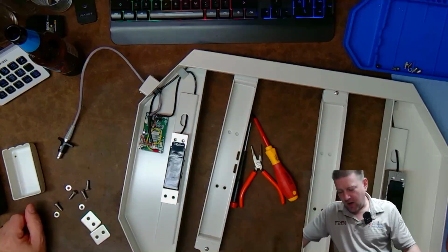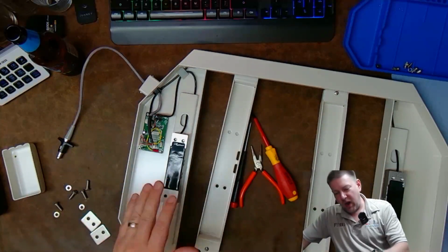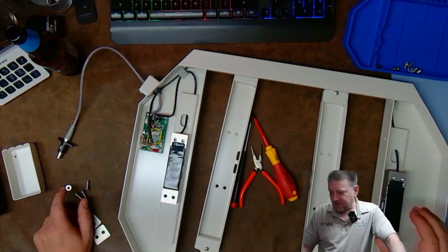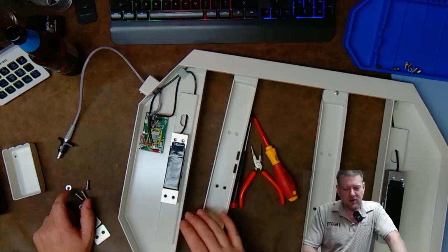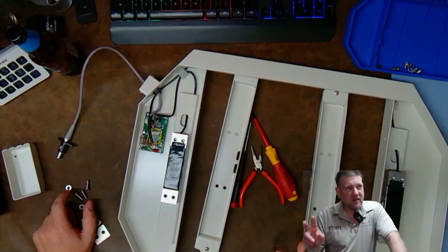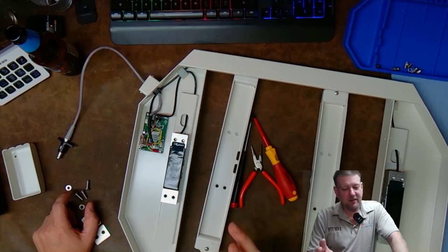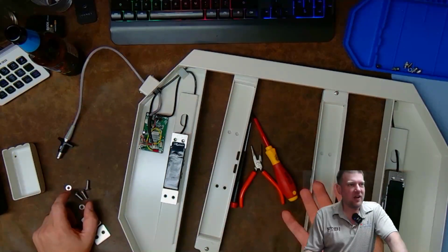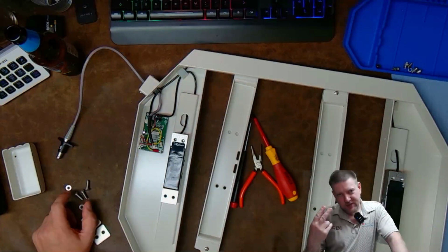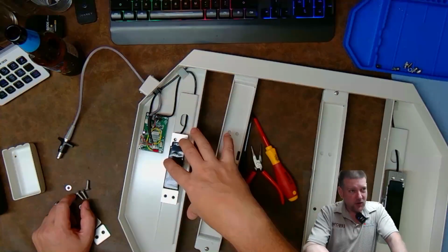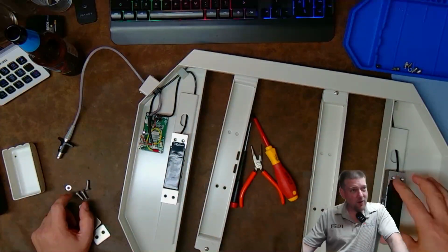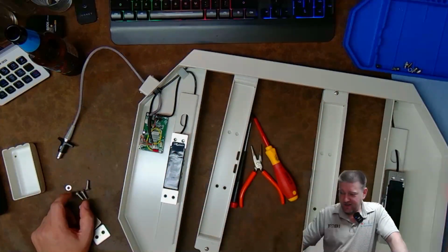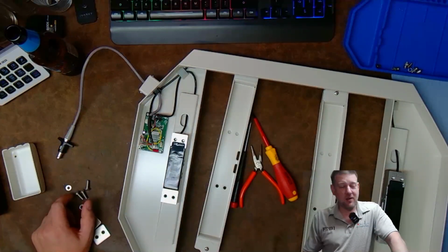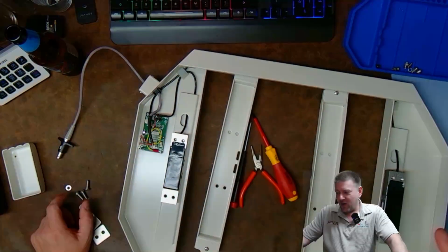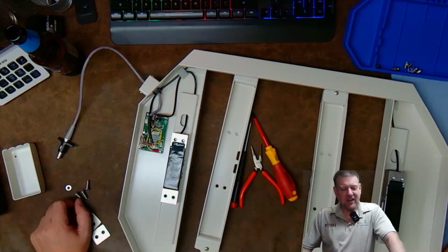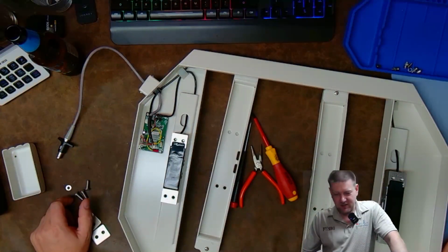Okay? So when you are putting a 5 kilogram weight on it, I can see already that it doesn't matter if it's in this corner, this corner, this corner, or this corner, because there's only 2 load cells. I was expecting 4 because it's a $3,000 scale. It's got 2 load cells. So you would move the weight up here in this corner, then you would move it down here. So move the weight from one side to the other. You've only got 2 values that you can change. So that would be 3 calibrations: 1 over here, 1 back here, 1 in the middle. Check it out and see if it clears.